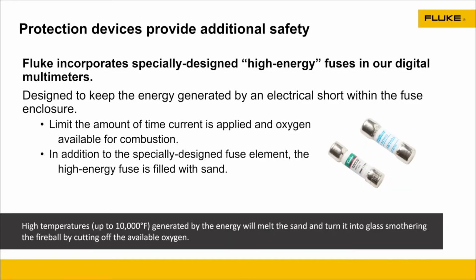Now with that, we talked earlier at the beginning of the slides about potentially having your test leads in the wrong position, making a voltage measurement when the meter thinks you're measuring a current. That'll go through the fuse, and hopefully that fuse will pop. You want to make sure you use the right fuses, designed for that meter, because that amount of energy can literally be up to 1,000 degrees Fahrenheit. Having the right fuse in there is really going to save you.